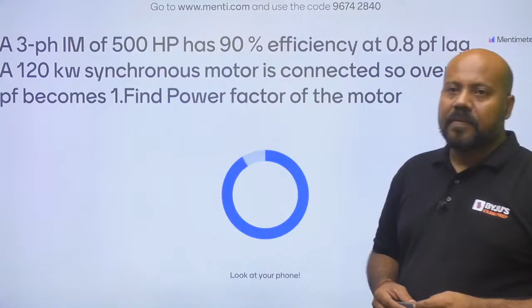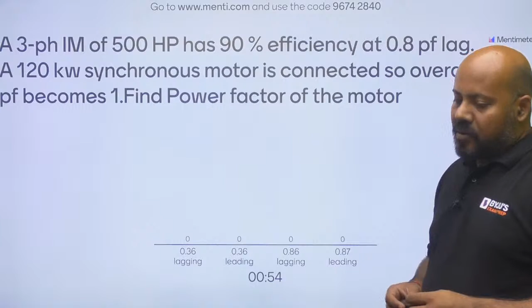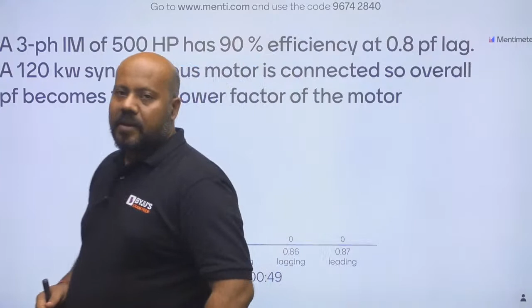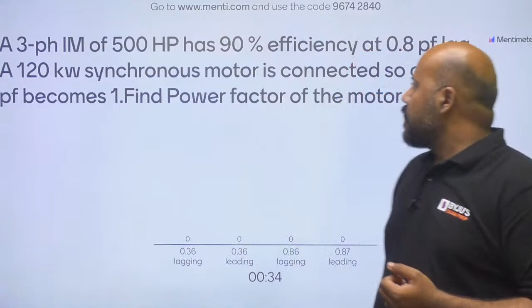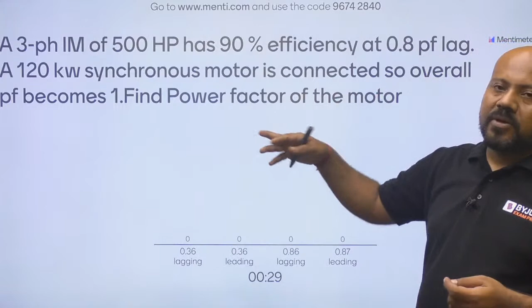See the question on your screen. Now this is a good question. This question is from dynamic compensation, synchronous phase modifier. Because the synchronous motor you are using here is not on no load. It is having some real load connected to its shaft. That is why it is saying a 120 kilowatt synchronous motor is connected. So overall power factor becomes unity.